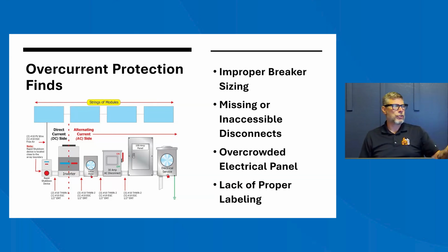The graphic over here shows the rapid shutdown off to the side. You do find them like that, but typically it's going to be at the base of your inverter and it'll say rapid disconnect. All of these should be clearly labeled. They need to be accessible and securely mounted. If they're missing a label, they're buried behind a water heater, or you're unable to access them, that's a major safety concern. You have to be able to get to these disconnects.